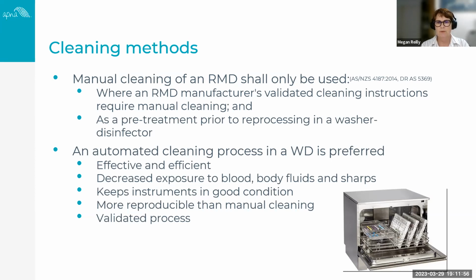So these are closed cabinets. They're linked to the water supply and to the drainage system. And they include a pre-rinse with water, a wash in warm water with a cleaning agent added. Then they have one or more rinses with hot water. So this achieves that thermal disinfection of between 80 and 86 degrees Celsius. And it has a drying agent added to it as well. Then we have the draining, so that actually leaves the contents at a temperature for quick drying. And then we have our drying process.